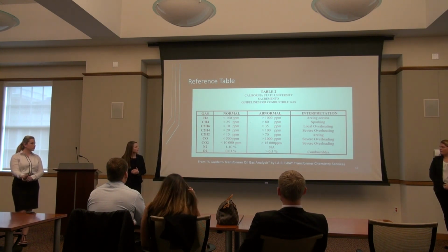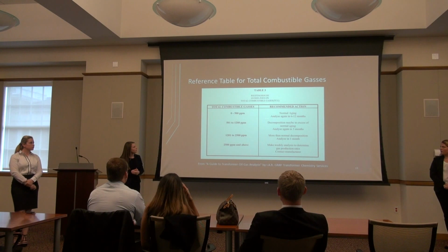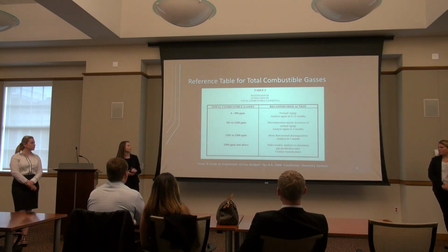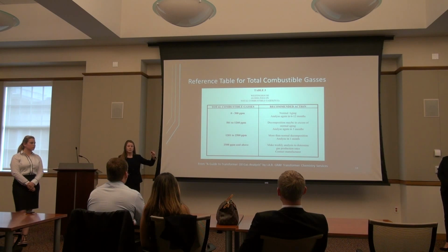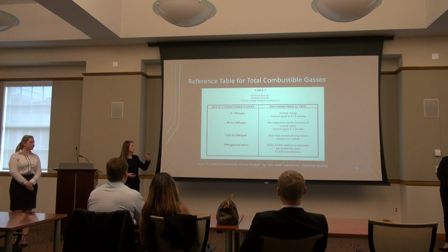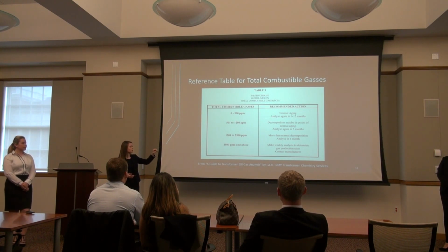So on the next slide, we see the total combustible gases. So instead of breaking down each gas by the normal and abnormal ranges only, we can also do it by interpreting the total combustible gases, which is an analysis of the total of all 10 gases. And there's 4 ranges here. So there's normal, decomposition, all the way down to bad decomposition, where you want to be testing that transformer weekly to make sure that nothing really bad is happening.